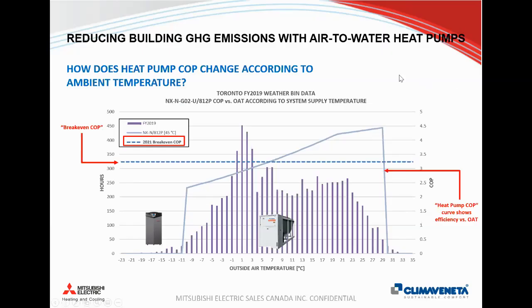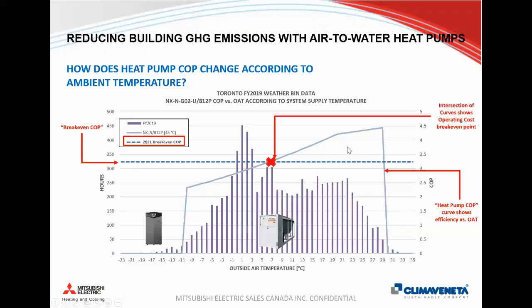So we're looking at COP here. And basically the COP will be at its maximum value at the warmest temperature because it's easy to extract heat. But then as it gets colder outside, your supply temperature might decrease depending on what you've selected it for. But the COP will also decrease. But the intersection of these two curves will tell us where it's automatically more economical to run a heat pump over a natural gas boiler.